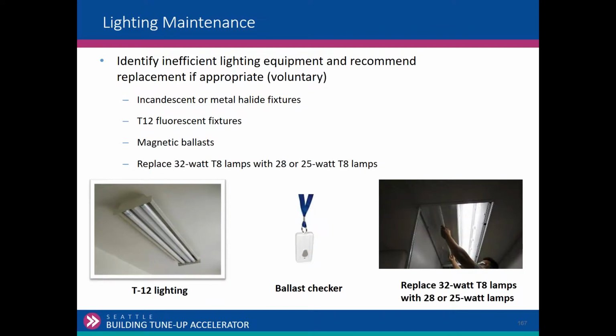So that's it on lighting. For the asset score, you need to know the approximate number of fixtures and type. I wouldn't spend the time counting every fixture in the building. I may look at a room, figure out the number of fixtures, divide that by the square footage. So now I have fixtures per square foot or square foot per fixture, and just use that for the building. That's going to give me my number of fixtures.